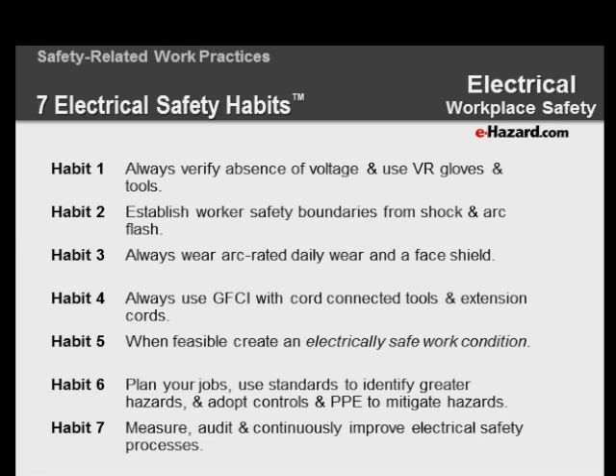Habit 1 was always verify the absence of voltage and use voltage-rated gloves and tools. The number 1 killer is shock, and if you use verification of the absence of voltage with a proper meter, checking the meter and checking the voltage, using voltage-rated gloves when required, and using insulated tools, you'll find that most of the fatalities will go away.